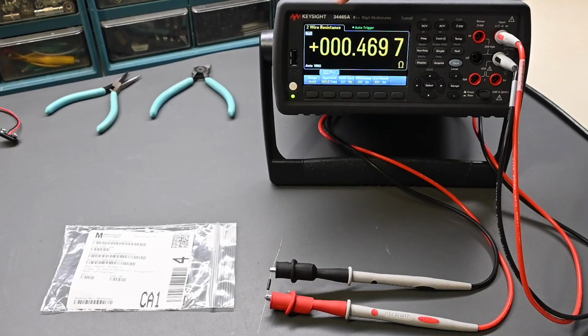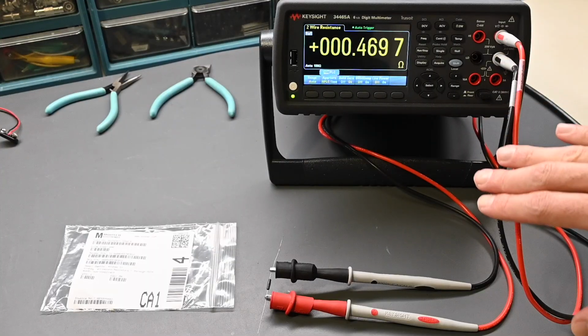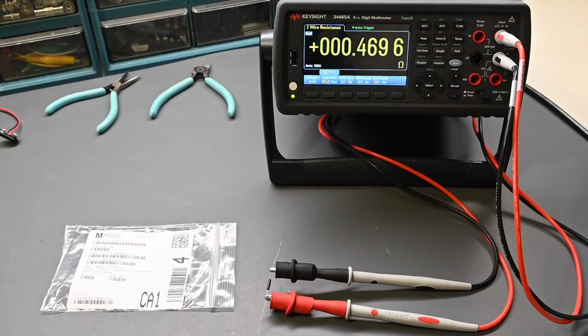And on the meter, it says null on the display right there, because the meter has been nulled out before I connected the resistor, to offset the resistance that's in the test leads. This is such a low value resistor that the resistance in these test leads would skew or cause an inaccurate reading. So the reading that we're seeing here is exactly the value of this resistor. It's very close to the promised value of 0.47 ohms, and again, it's a 1% tolerance.